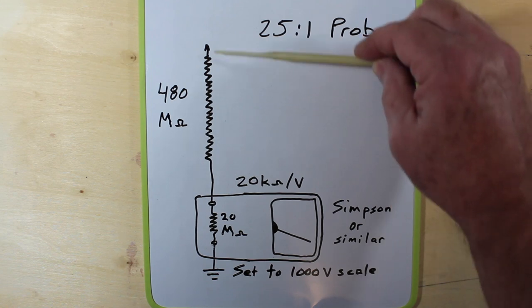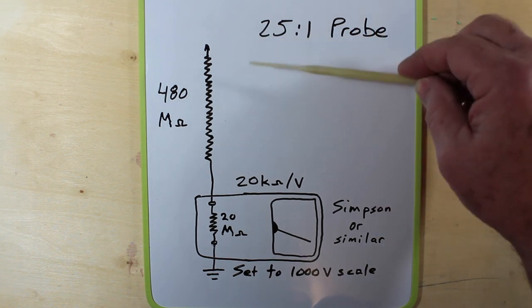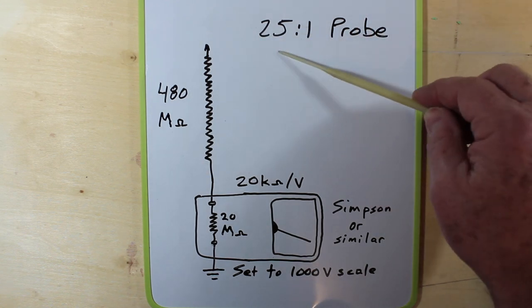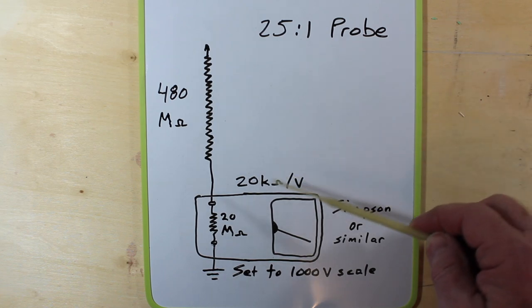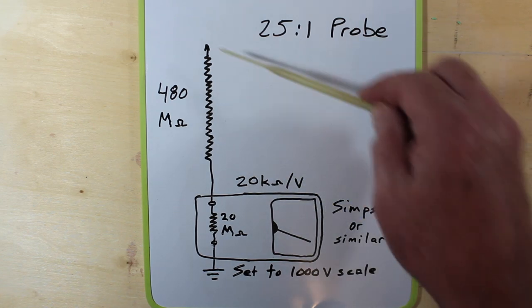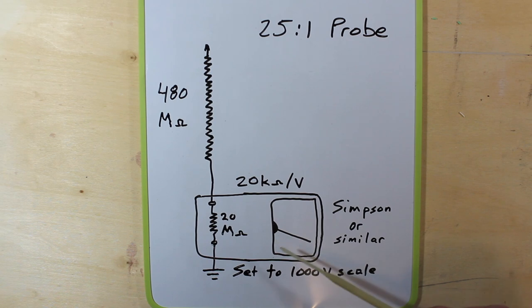That 20 mega ohm in series with the 480 that's in the probe, the 480 megs, gives us a 25 to 1 situation. So when we have 25,000 volts here, this will be full scale on the 1,000 volts because it's divided down by 25.